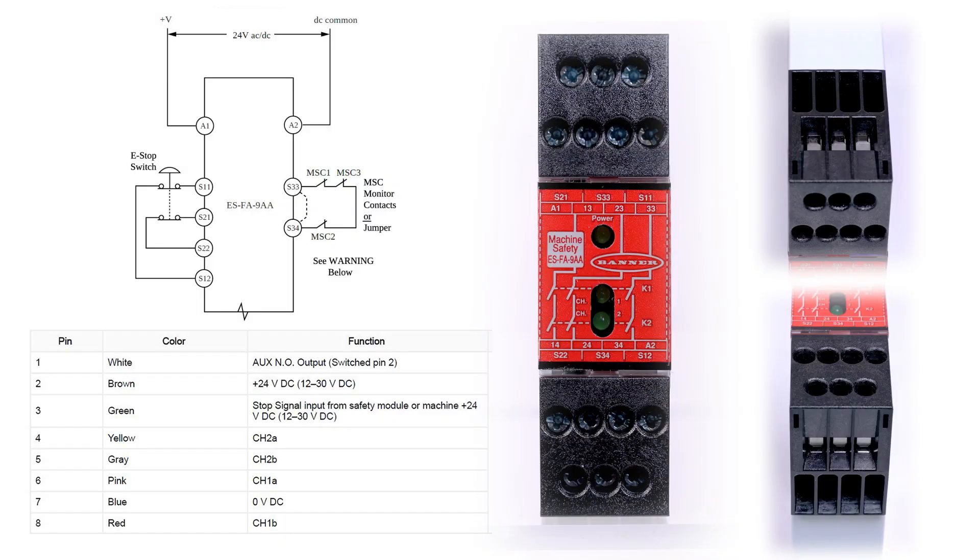If you require contact monitoring, you will need to wire the appropriate contacts to terminals S33 and S34. If you do not need monitoring, add a jumper wire to these terminals.